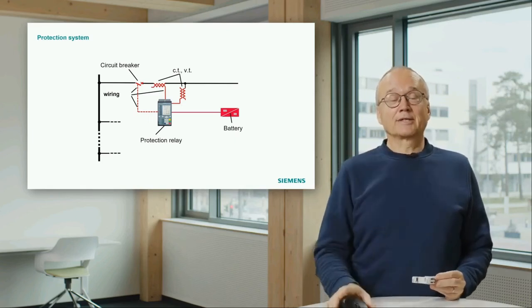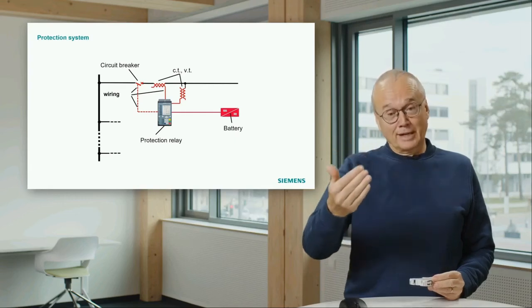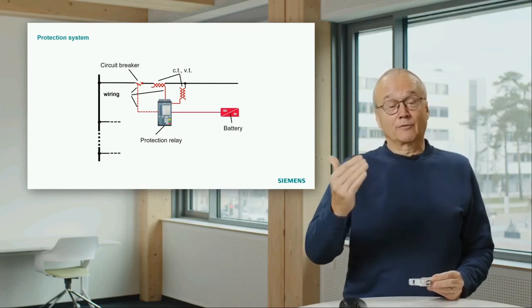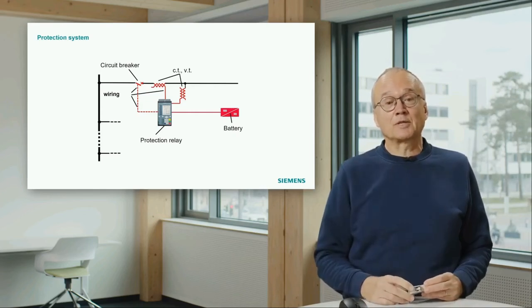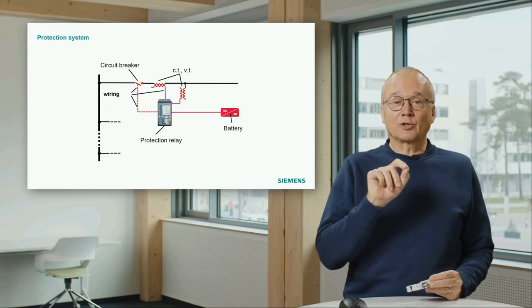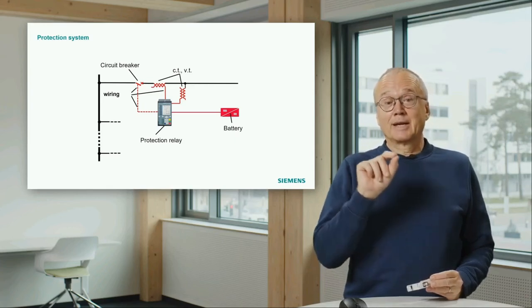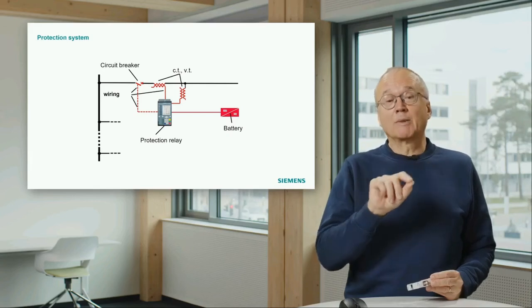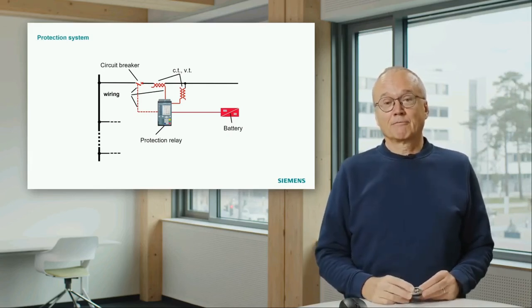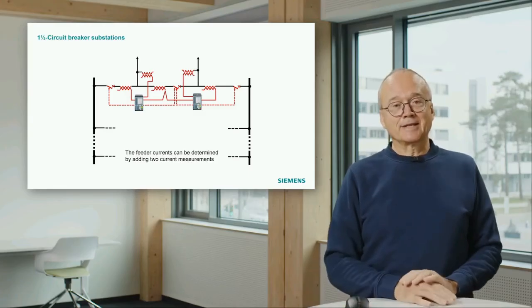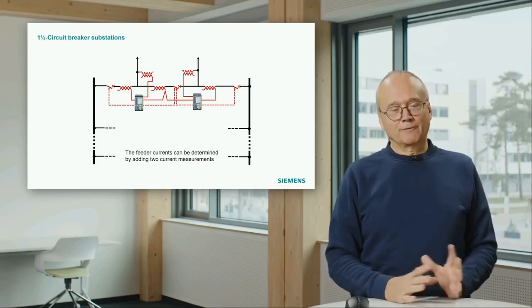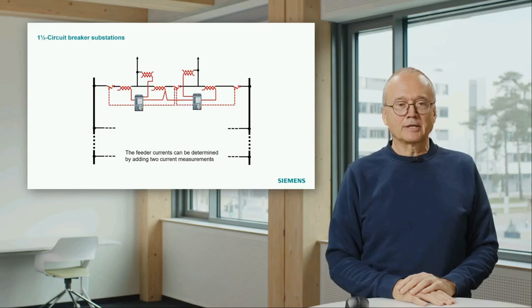What our protection does is only half of that. It cannot measure the current directly. It gets the current and voltage measurement through current and voltage transformers. But the important thing, it cannot interrupt the current itself, it can only give a trip command to a circuit breaker. That means our protection relay roughly does half the job of such an MCB, but of course in a much more sophisticated way. What you also sometimes find is this arrangement, which is unfortunately a little bit more complicated.